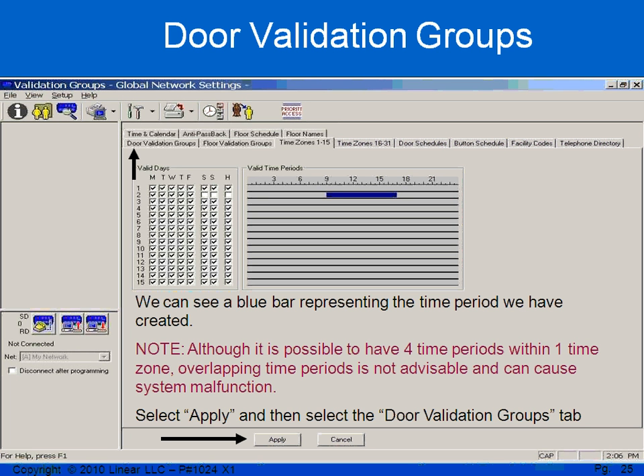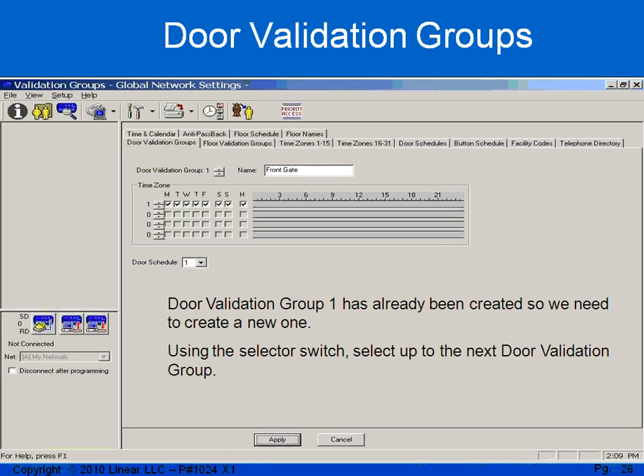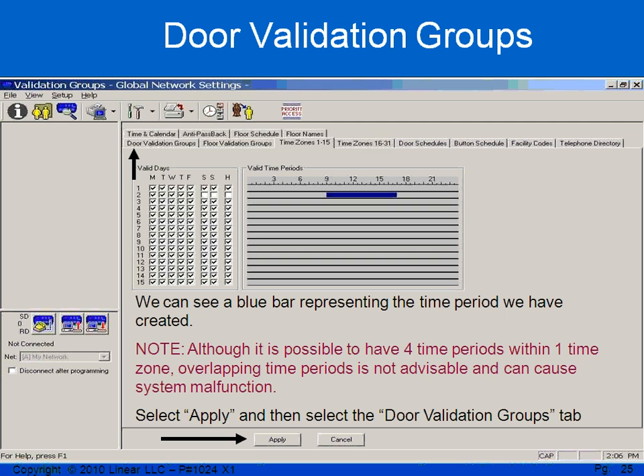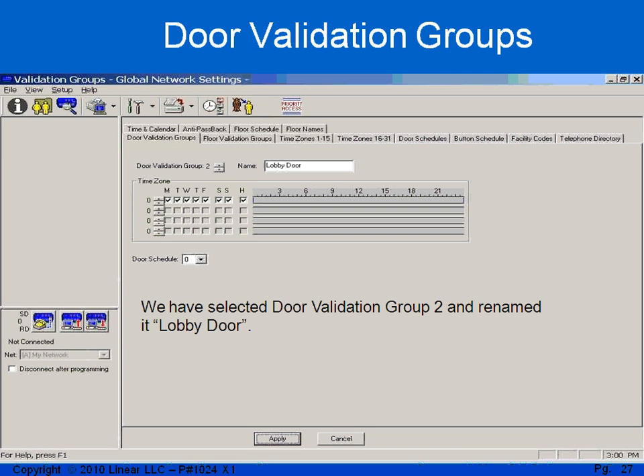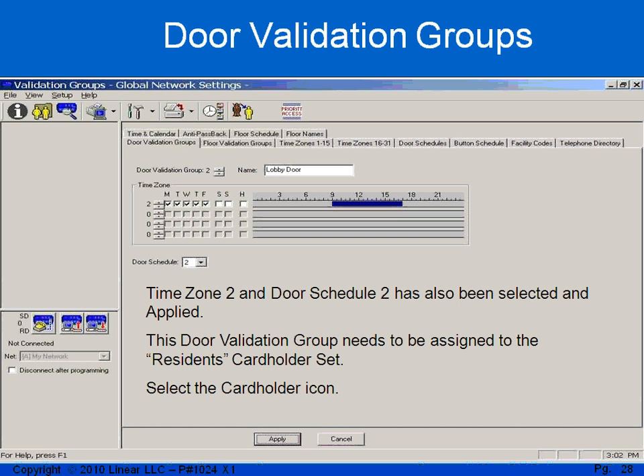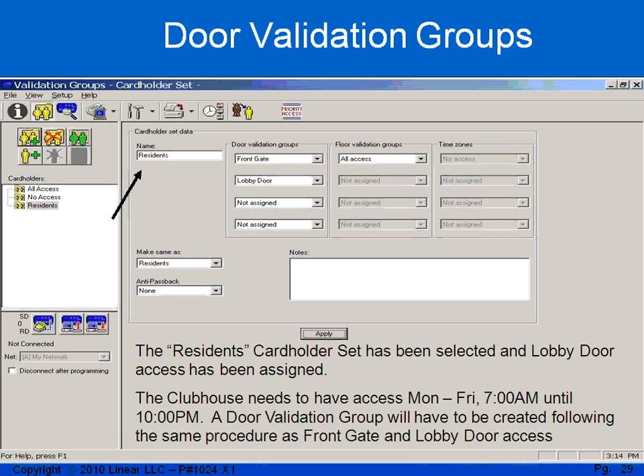Now that I've created my door schedule and my time zone, I need to roll that into a validation group. I select door validation groups. I've already used door validation group 1, so I need to select door validation group 2. I'm going to label it lobby door. I select time zone 2 and door schedule 2, and I apply. Next, I need to take this validation group and assign it to my cardholder set, so I select the two yellow people, select my cardholder set, and give them the lobby door validation group.